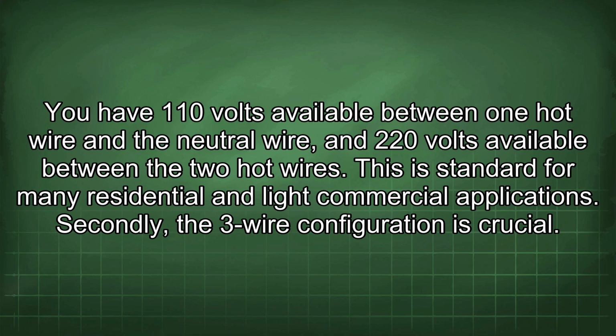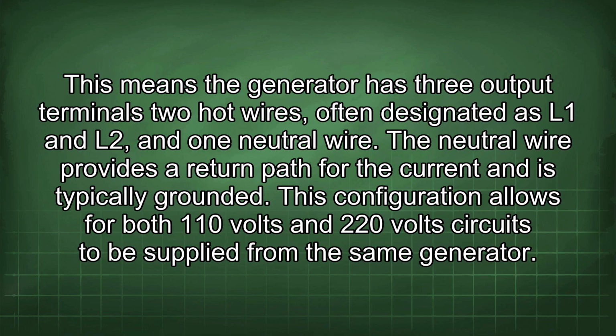Secondly, the three-wire configuration is crucial. This means the generator has three output terminals, two hot wires, often designated as L1 and L2, and one neutral wire. The neutral wire provides a return path for the current and is typically grounded. This configuration allows for both 110 volt and 220 volt circuits to be supplied from the same generator.